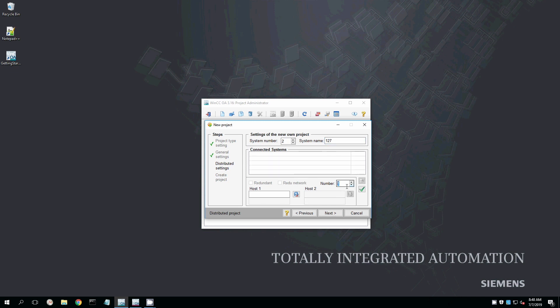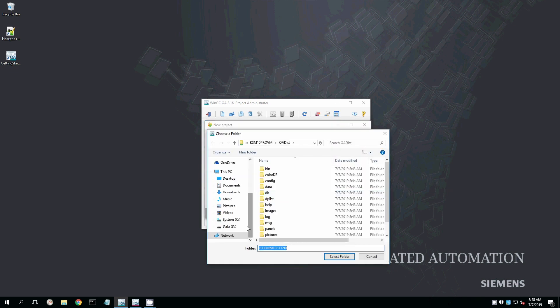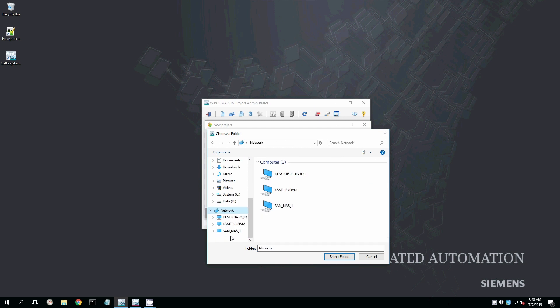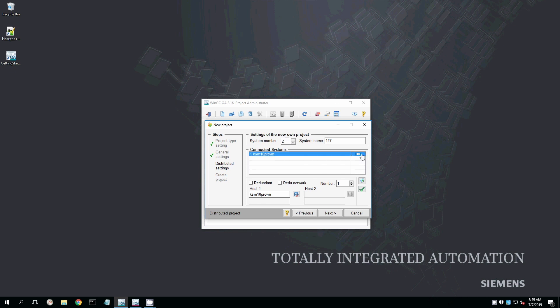Now, what I really like about WinCC OA is that it's the same installer for a small microcomputer like this and a full-blown server. So we did a full installation. It's 1.4 gigs for the Windows installer, and I created a distributed application, and then I pointed it at the application that's running on the WinCC OA server.